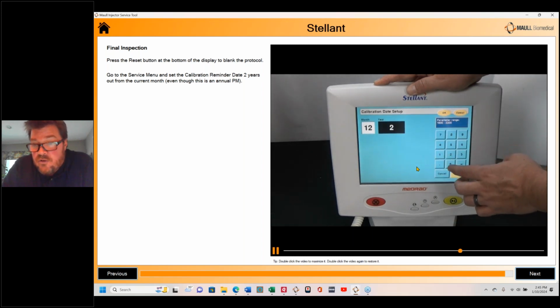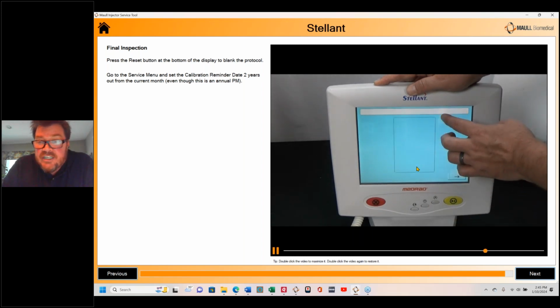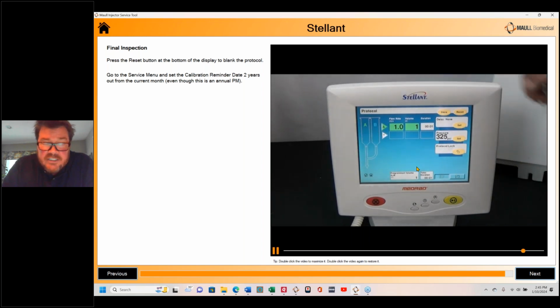Now, this is an annual PM, but if we set that date 1 year out, when we get within 1 month of that date, a little message starts popping up on the display telling the operator, hey, this thing needs calibration. It's on your schedule. You don't need the operator calling you up telling you that it needs a calibration or maintenance or anything like that. It's on your schedule. You'll be in there next month to do it. And you can't turn that cal date reminder off. So we just set it 2 years out so it's not popping up for the operator to see it when it's not necessary.